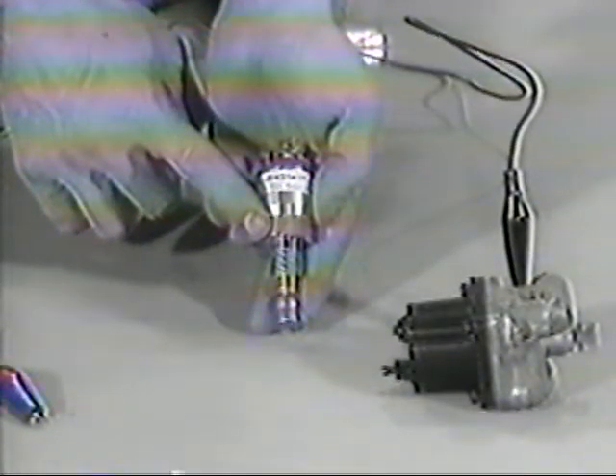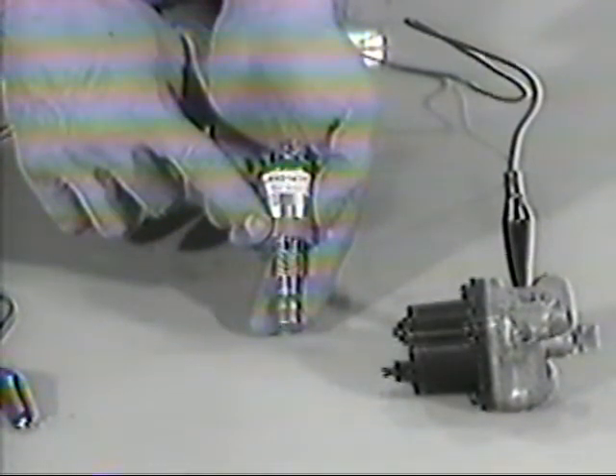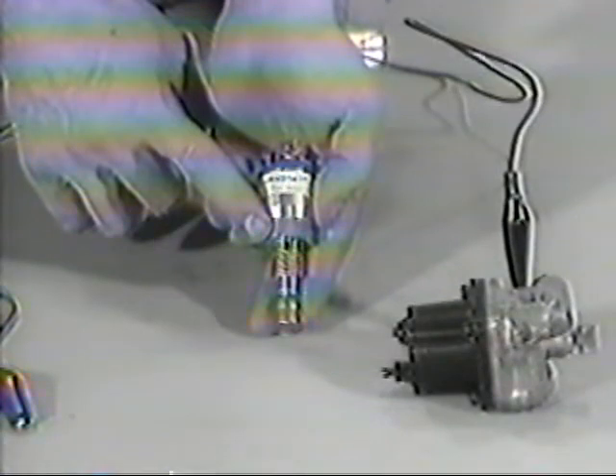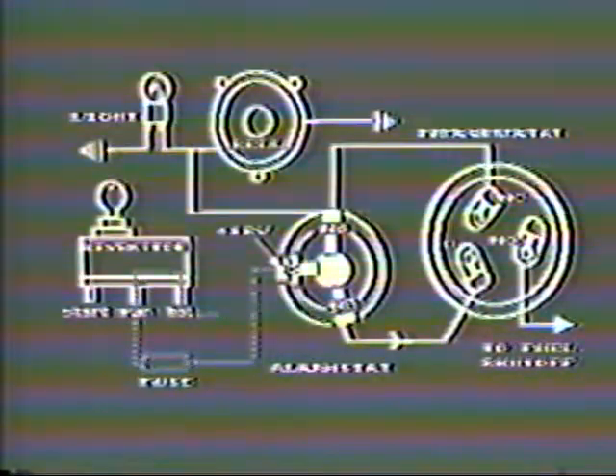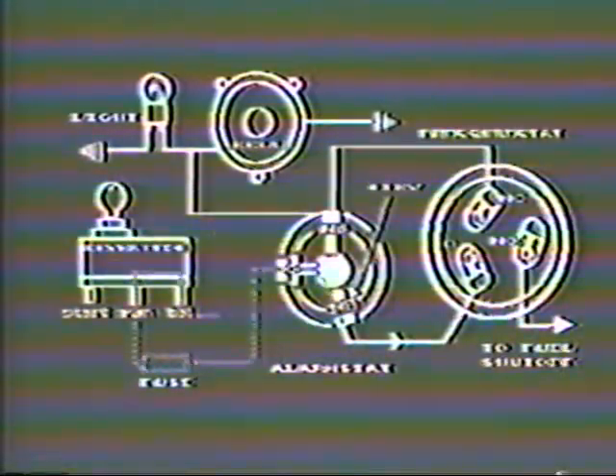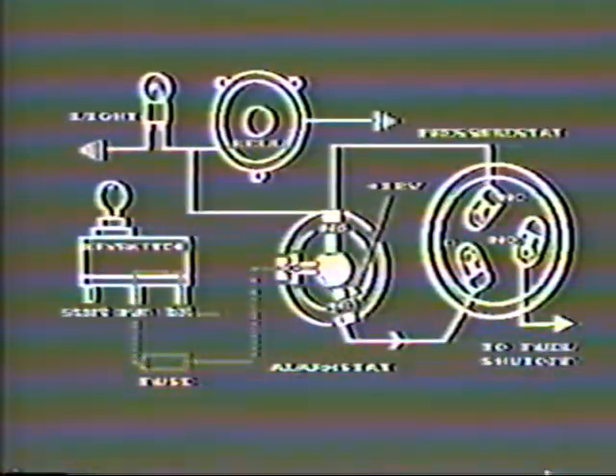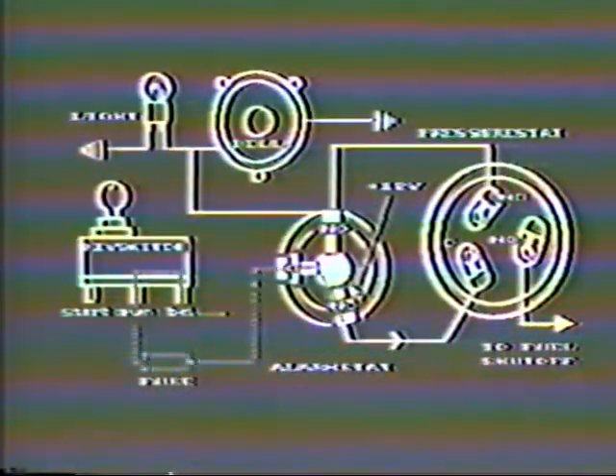The alarm stat, or temperature sensor, will be the first. The setting on this one is 220 degrees Fahrenheit. That means it will give a high temperature alarm at 214 degrees and shut the engine down at 220 degrees. Electrically, it looks like this, with voltage from the key switch reaching the alarm stat at the C, or common terminal. The normally closed switch is the one set at 220 degrees. So as long as engine temperature remains below that, the switch is closed and we have voltage at the NC terminal. A wire connects alarm stat NC with pressure stat C, so there is voltage there also.